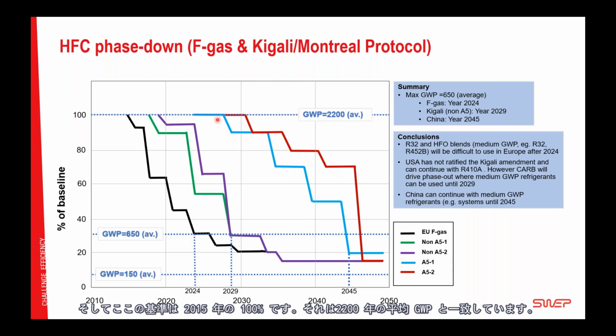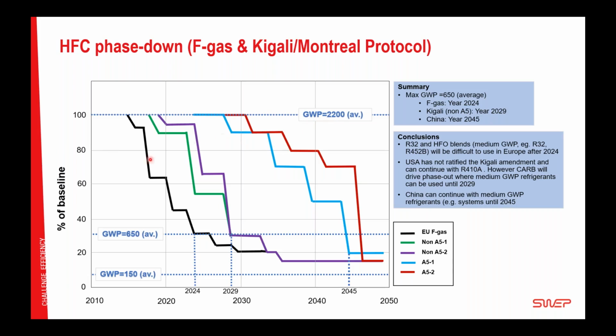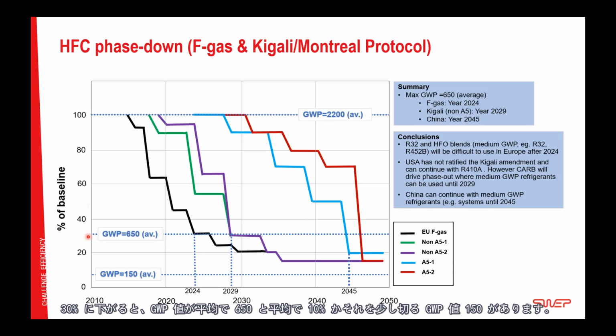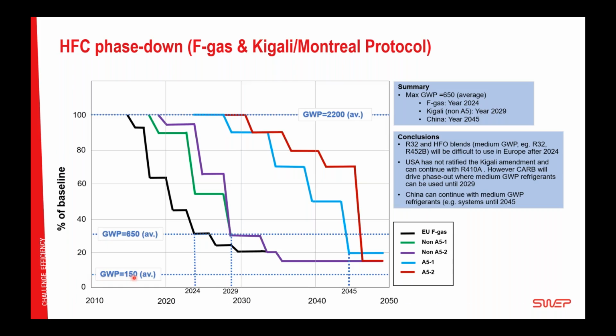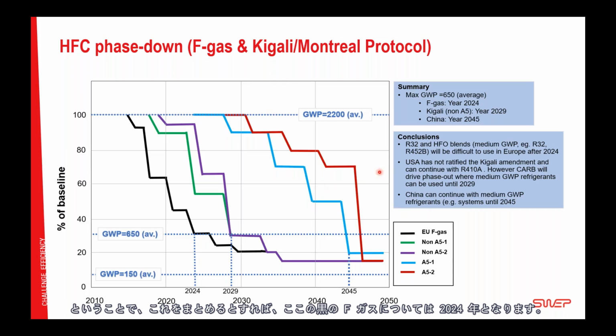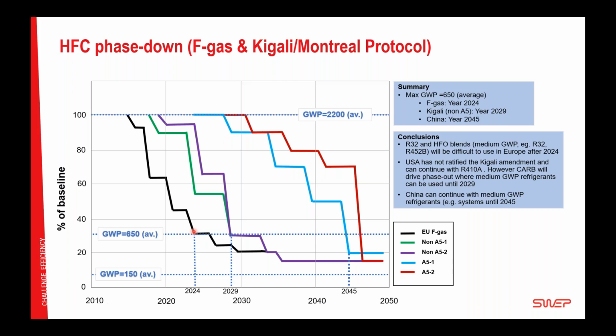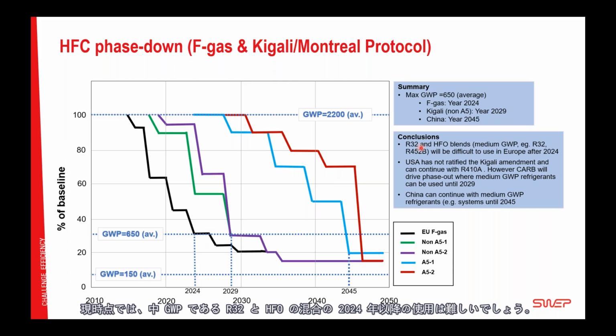2015, and that corresponds to a GWP of 2,200 on average. Moving down to 30%, we have a GWP of 650 on average, and at 10% or slightly below, a GWP of 150 on average. So if we try to summarize this, we can see with F-gas, which is the black one here, 2024, at this point, it will be difficult to use R32 and HFO blends, that is medium GWP, after 2024.